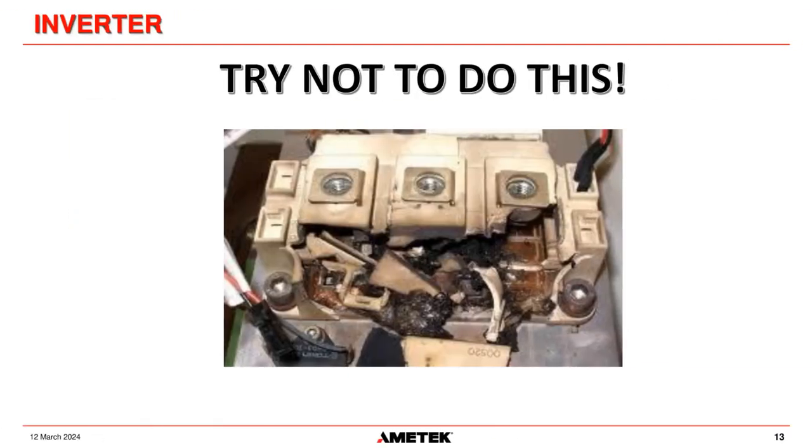Okay, this is what they shouldn't look like inside a power UPS. Yes, please try not to do this. This is what happens when too much current flows through an IGBT. It destroys itself. They're very, very sensitive devices to high current. And unlike SCRs, which can tolerate a high amount of fault current, IGBTs will pretty much blow themselves to pieces when they have higher than the acceptable current going through them. So try not to do that.